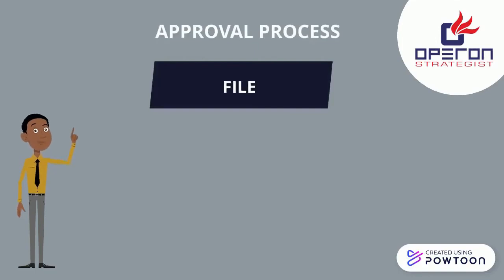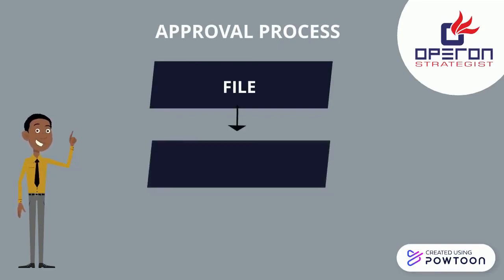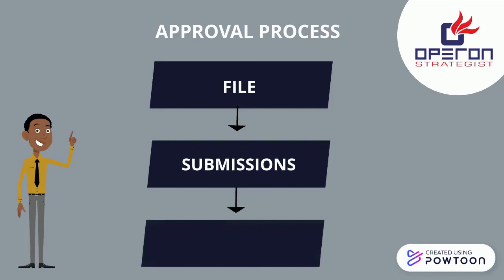Approval process. File. The medical device related document for CE, US FDA and CDSCO have adequate data for the respective agencies to audit and approve. Submissions. This document is submitted to either a notified body in case of CE, or to FDA for 510(k), or to CDSCO for manufacturing license. Approvals. These are the regulatory bodies which review the files and may have certain queries or observations for the documents. Upon successful justifications to the queries, they issue the approval in their respective ways.